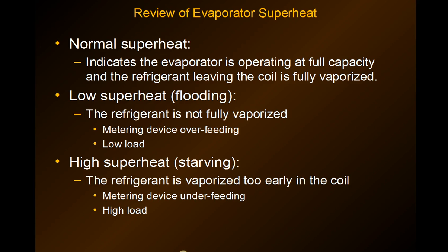High superheat means you have a metering device that is underfeeding, which could be a bad TXV, a plugged cap tube, or someone has loaded higher-temperature product into the box than what the box was designed to hold — and that's going to give you high superheat as well.